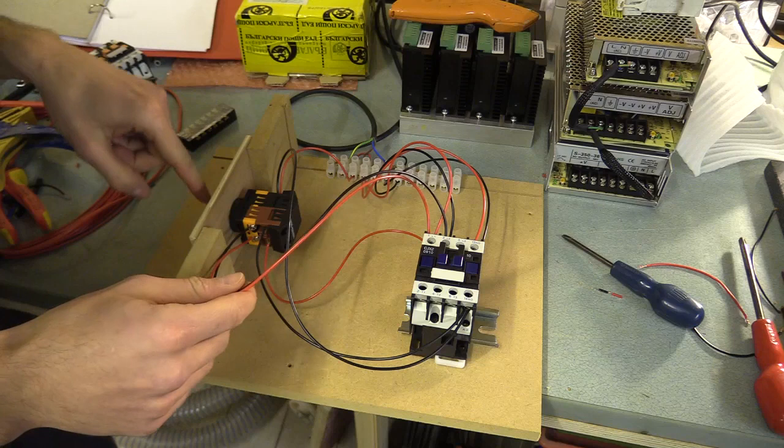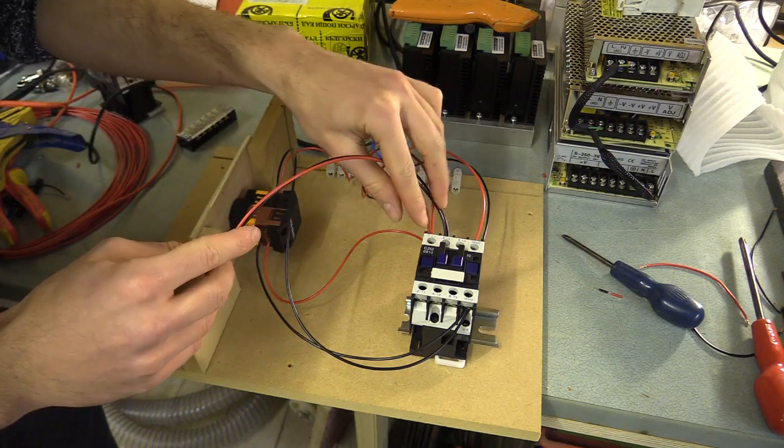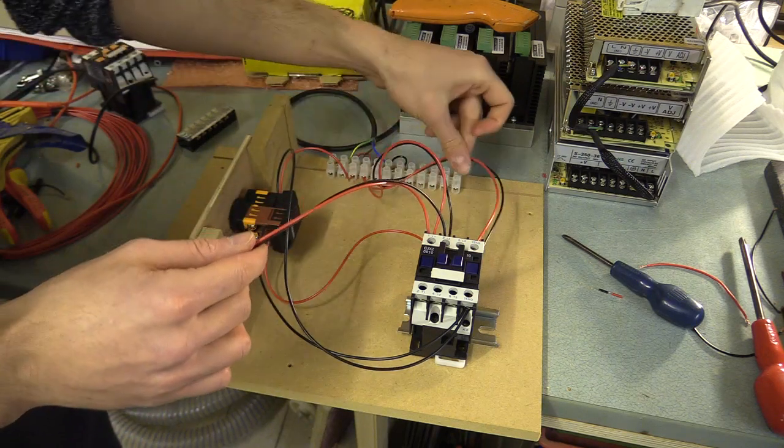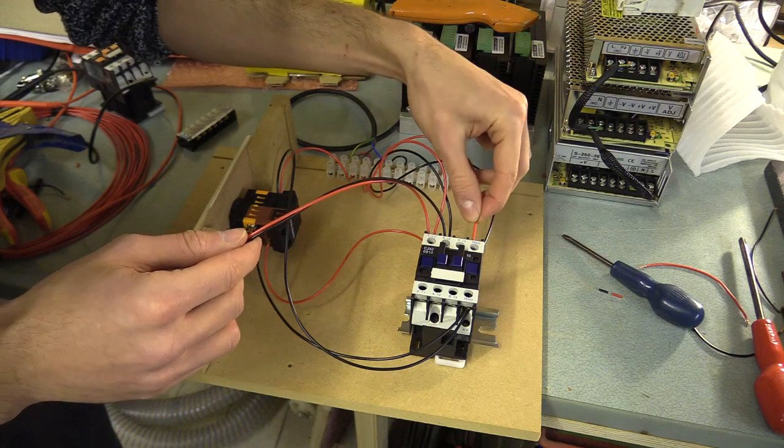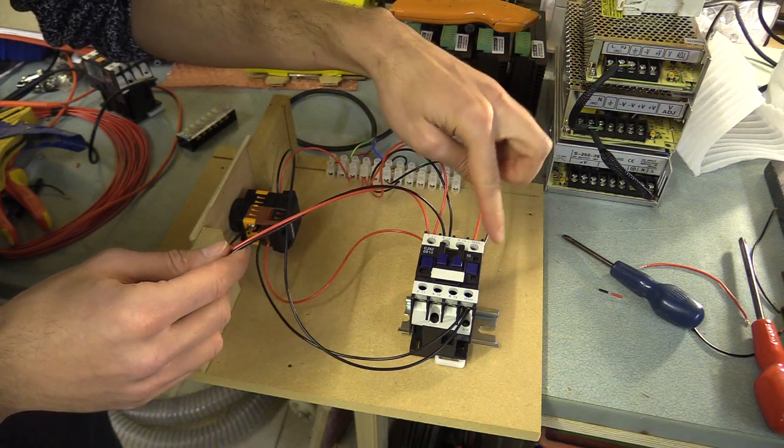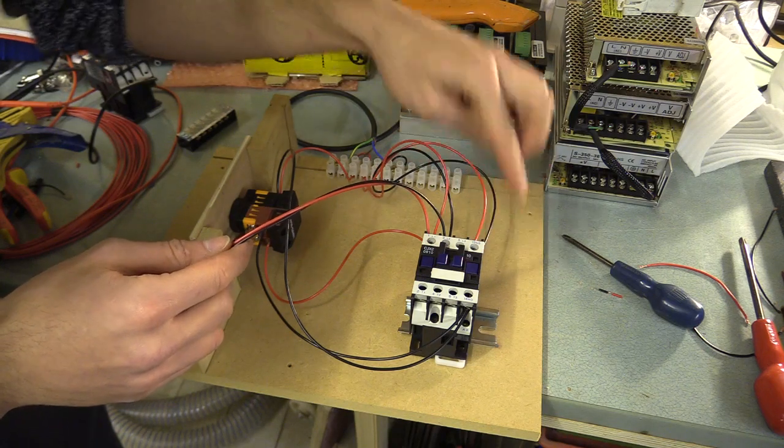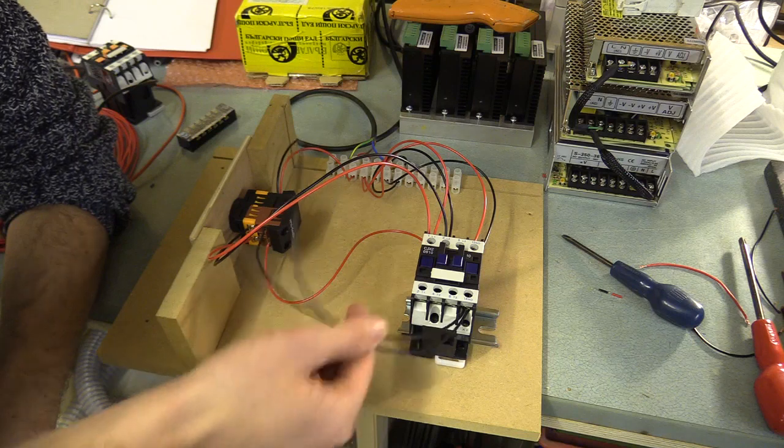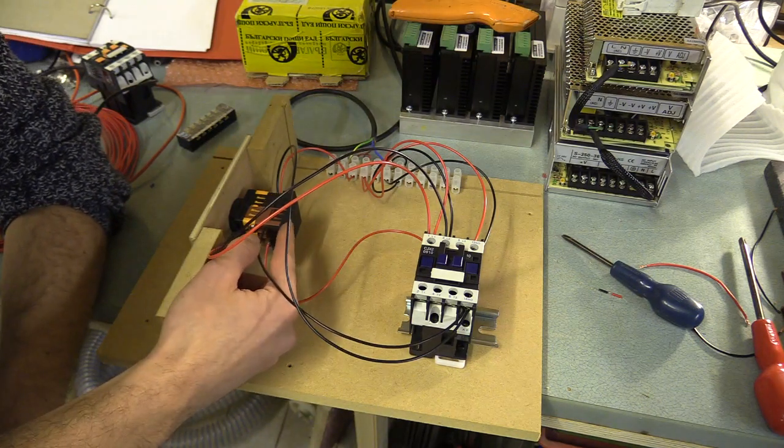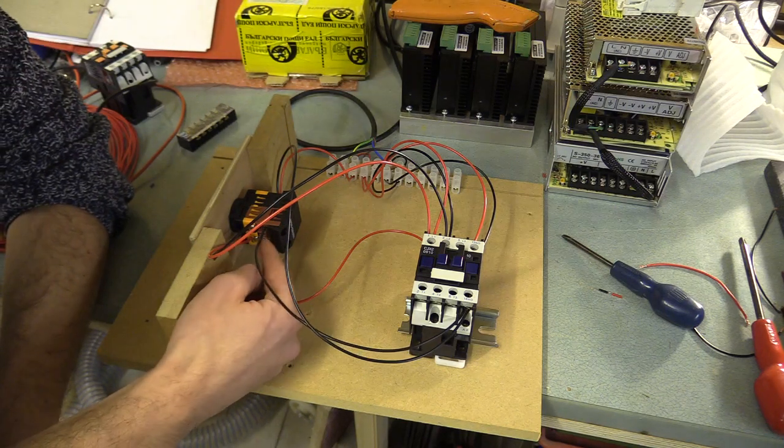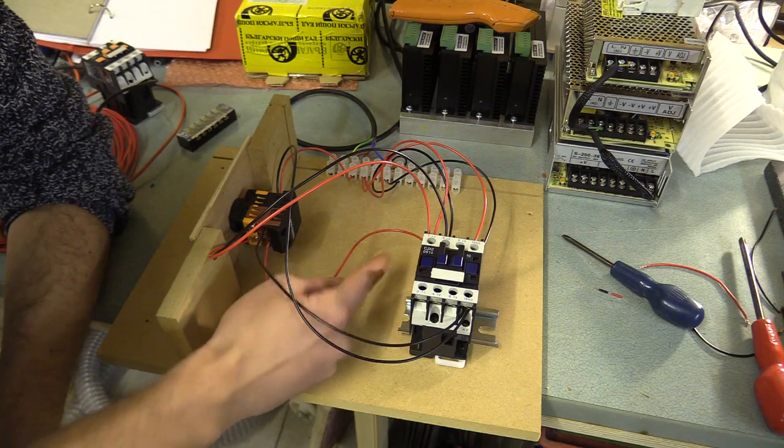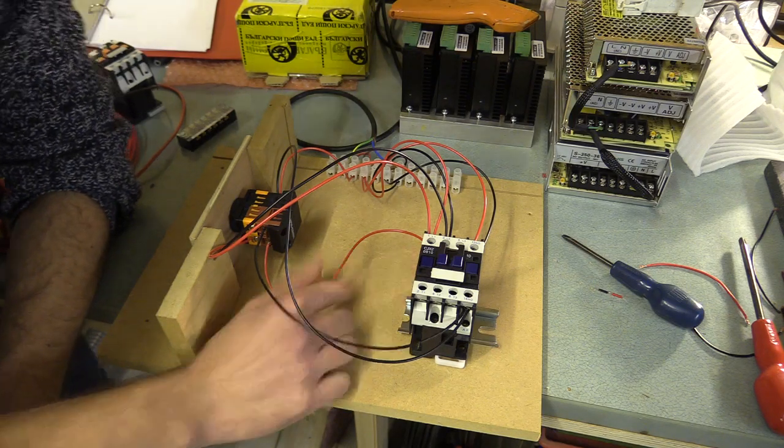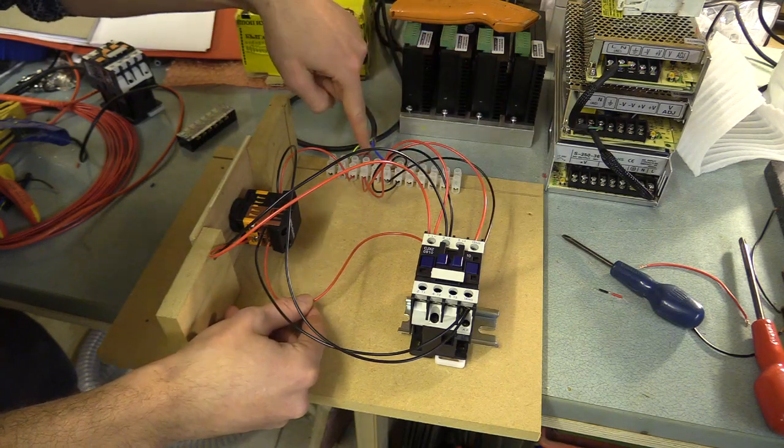So I've wired the light on the actual switch into the L1 and L2 terminals which go to live and neutral. I then have a live wire coming to the normally open terminal at the end of this unit, and it comes out to - really this should be red - to the off switch, which should be normally closed. And then carries on going through the switch to A1, which is the entrance terminal to the coil. And then A2 goes directly back to neutral.